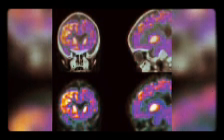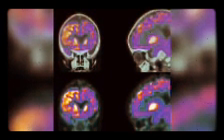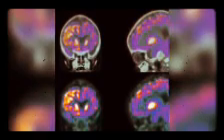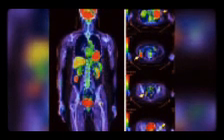1. Treat each ring as a separate entity, so that only coincidences within a ring are detected. The image from each ring can then be reconstructed individually, 2D reconstruction, or 2. Allow coincidences to be detected between rings as well as within rings, then reconstruct the entire volume together, 3D.